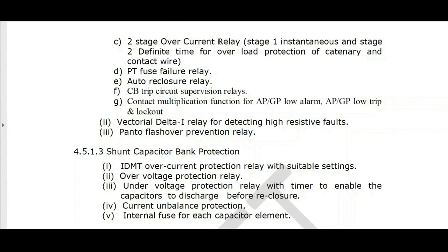So it's just an overcurrent function. It acts as a non-unit protection with a definite time. So earlier we saw IDMT, inverse definite minimum time. That is for the transformer. For the catenary wire, that is, the 25 kV line is called the catenary wire, we have to provide definite time.